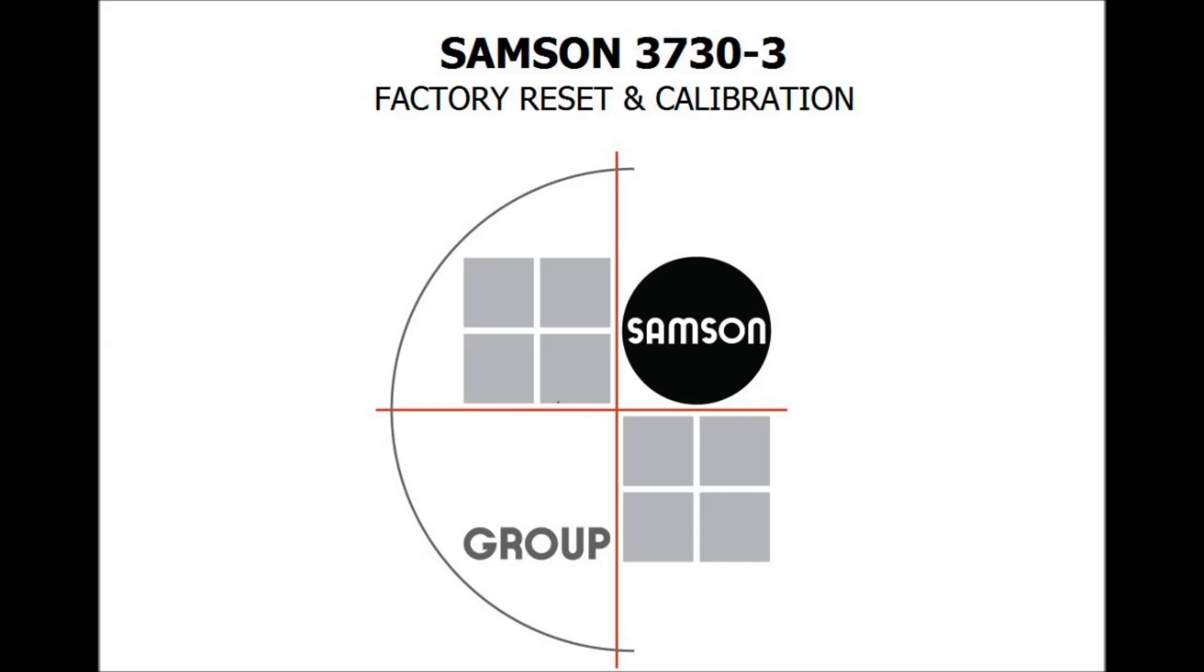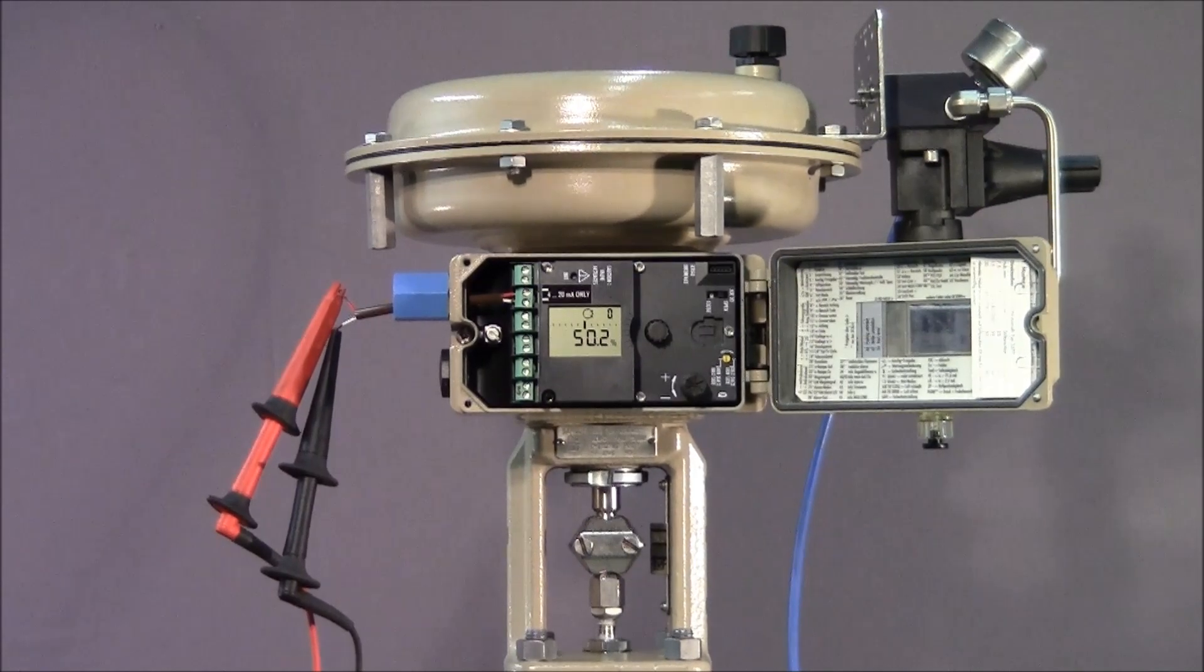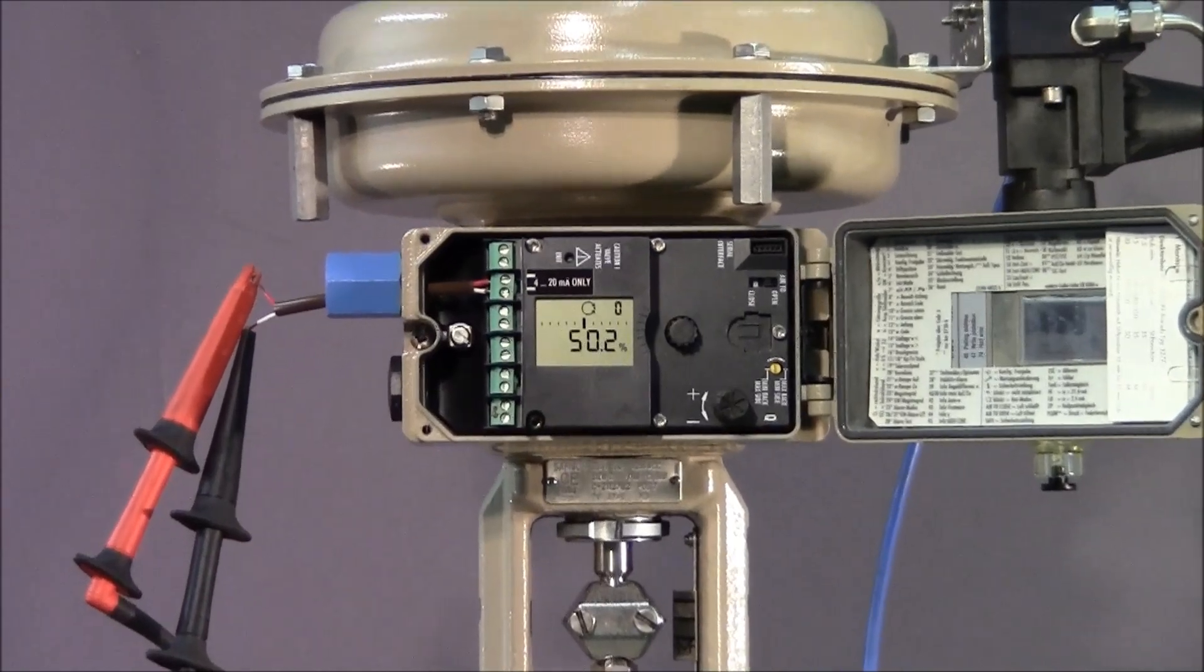In this short how-to video, we'll illustrate how to reset a 3730-3 positioner to factory default settings and perform an auto-calibration. Detailed step-by-step instructions can also be found by following the link below. This process should be performed after conducting any maintenance requiring valve disassembly or if you're experiencing positioner problems resulting in erratic valve behavior.